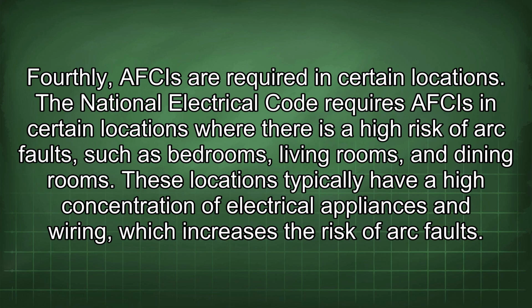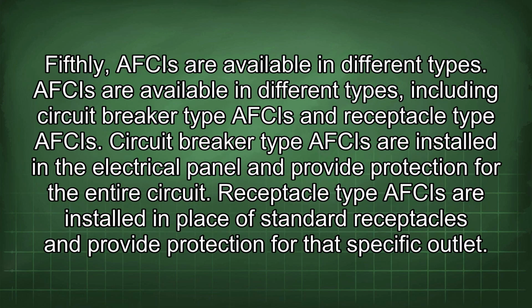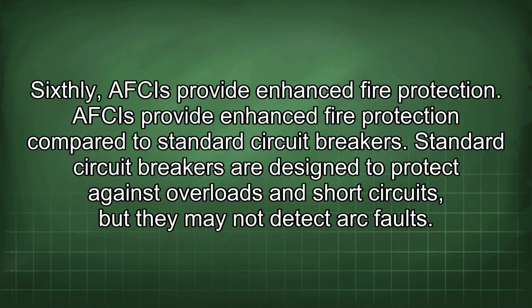Fourthly, AFCIs are required in certain locations. The National Electrical Code requires AFCIs in certain locations where there is a high risk of arc faults, such as bedrooms, living rooms, and dining rooms. These locations typically have a high concentration of electrical appliances and wiring, which increases the risk of arc faults. Fifthly, AFCIs are available in different types, including circuit breaker type AFCIs and receptacle type AFCIs. Circuit breaker type AFCIs are installed in the electrical panel and provide protection for the entire circuit. Receptacle type AFCIs are installed in place of standard receptacles and provide protection for that specific outlet. Sixthly, AFCIs provide enhanced fire protection compared to standard circuit breakers.